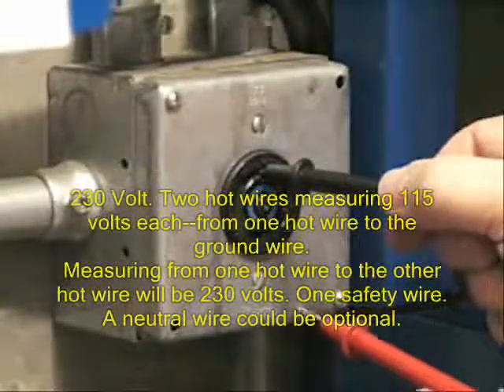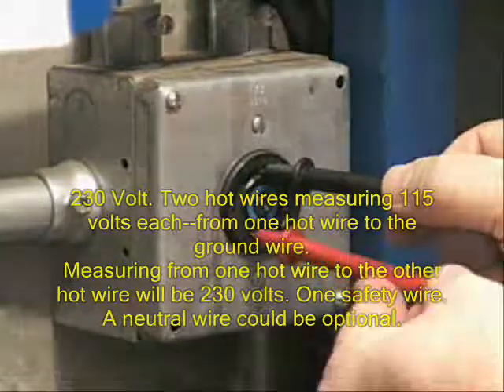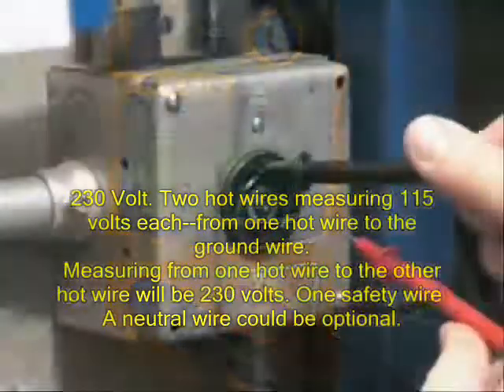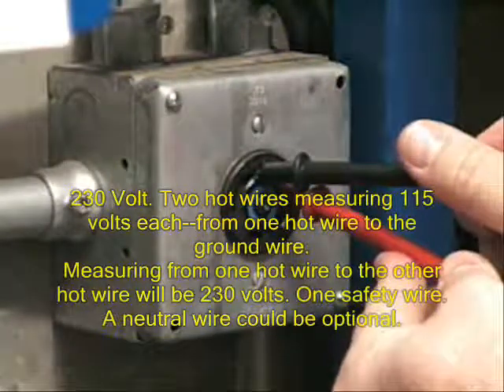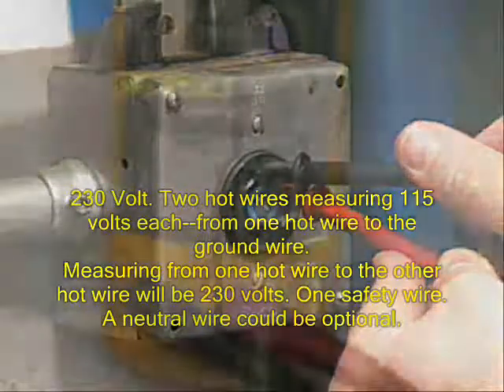230 volt. 2 hot wires measuring 115 volts each from 1 hot wire to the ground wire. Measuring from 1 hot wire to the other hot wire will be 230 volts. 1 safety ground wire. A neutral wire could be optional.